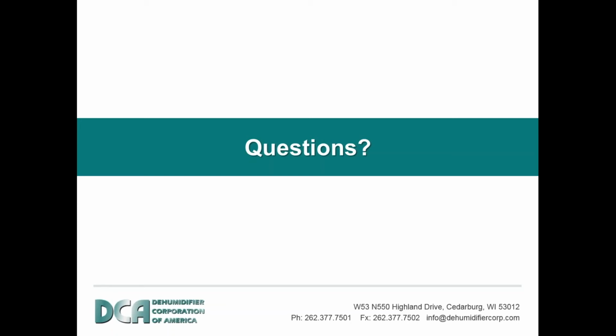Harry, this is a great question, and one that we see just about every time it's time to replace the dehumidifier. And this is a great time to address the problem. Was the right unit put on the job to begin with? With that, we have a load information sheet on our website that asks all the appropriate questions, and that being the surface area of the water, the hot tub, the volume of the room, the duct system, the amount of glass that we're going to experience, obviously where the unit is located, what part of the country makes a difference. If it's a commercial application, the amount of outdoor makeup air, and any of these questions that are asked for on that sheet. This is a great time to determine if the one you have is the right one. If it isn't, now we can make the change.